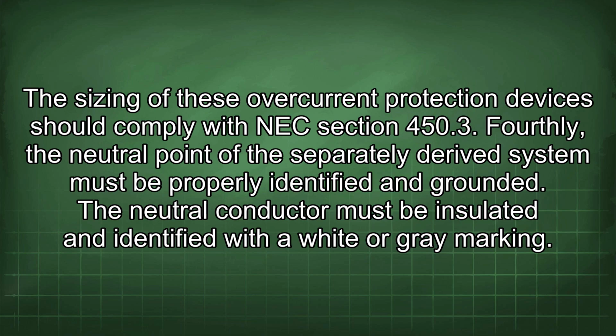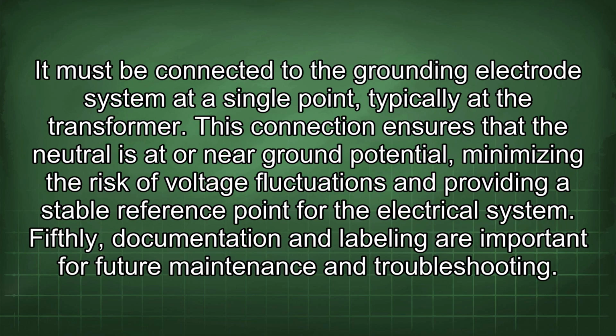Fourthly, the neutral point of the separately derived system must be properly identified and grounded. The neutral conductor must be insulated and identified with a white or grey marking. It must be connected to the grounding electrode system at a single point, typically at the transformer. This connection ensures that the neutral is at or near ground potential, minimizing the risk of voltage fluctuations and providing a stable reference point for the electrical system.